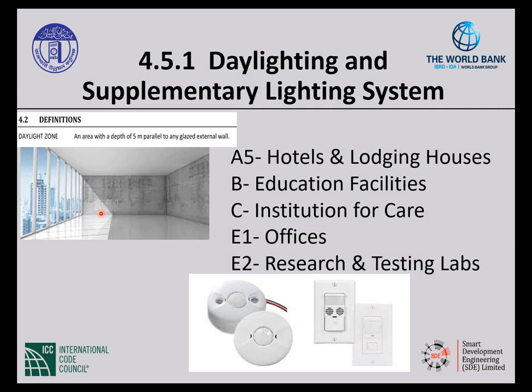And then it says if occupancy sensors are installed in that daylight area, the occupancy sensors shall override the daylight sensors during non-occupancy period. So I have a room. Maybe it requires an occupancy sensor. It's a conference room or something, and it requires an occupancy sensor. But I also have this daylight sensor that's sensing how much daylight, which one prevails? The occupancy sensor. There's no reason for that daylight sensor to be turning the lights on and off if nobody's in the space. So this is telling us that it wants that occupancy sensor to overrule the daylight sensor.